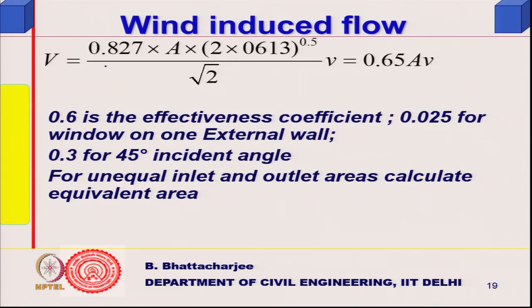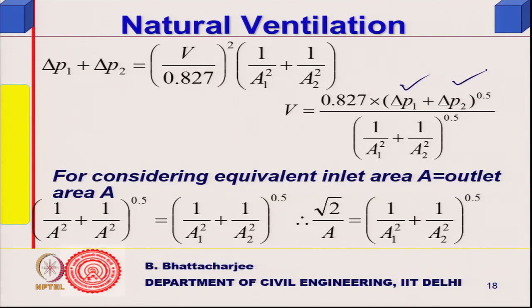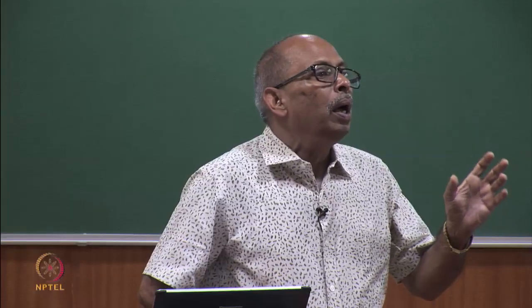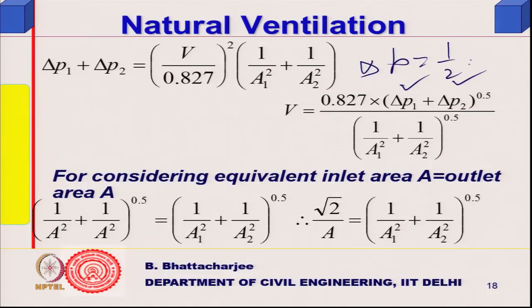Flow is simply 0.827 times A times delta P to the power 0.5, with total delta P taken as delta P1 plus delta P2. Pressure can be written as half-rho times v-squared. Half-rho equals 0.613, because the density of air is approximately 1.2 kg/m³.